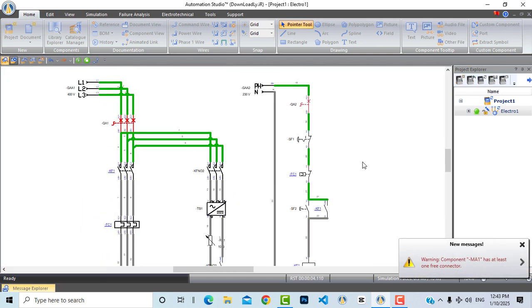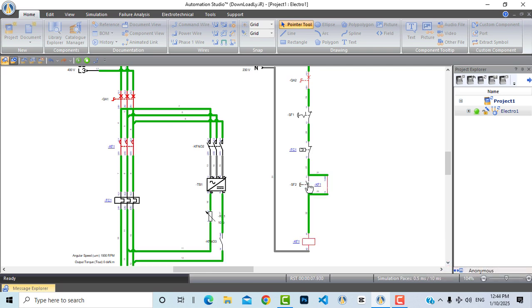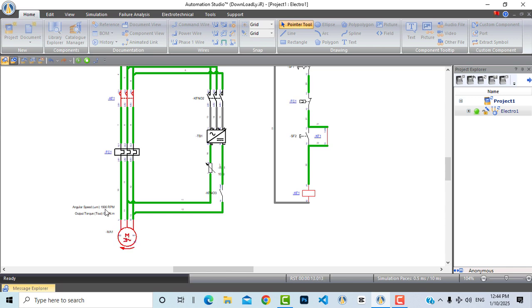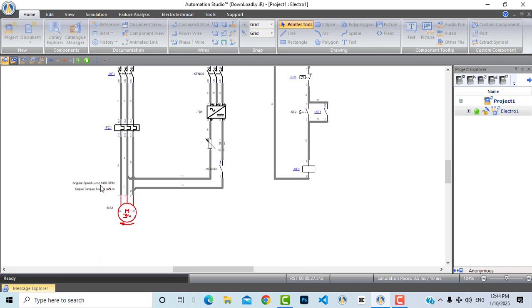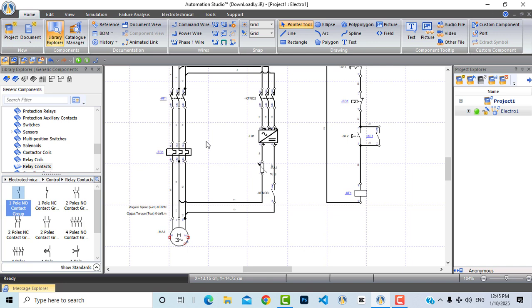If we simulate this circuit now we will see the motor working as a direct online circuit. Close the circuit breaker, then press the start push button and the motor starts working at maximum speed. Now if we stop it, the motor will stop but only after a specific time because of inertia. We use DC injection braking or other braking methods to stop the motor instantaneously — for example, with an overhead crane, you want it to stop instantaneously when you release your hand.